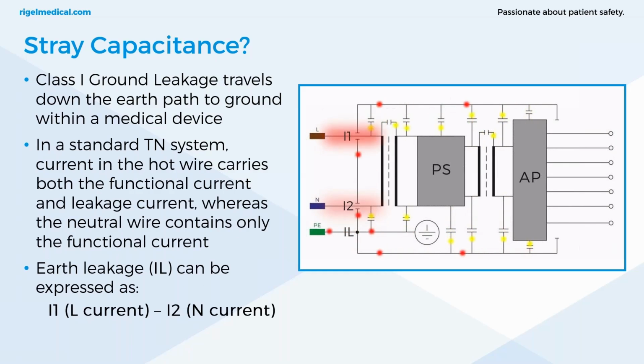So class 1 ground leakage travels down the earth path to ground within a medical device in a standard TN system. Current in the live wire carries both the functional current and the leakage current, whereas the neutral wire only contains the functional current. There is a method within a different standard, 62353, whereby the leakage current is measured by looking at the imbalance between these two connectors. But the preferred method is to measure it directly. So the live carries the functional and leakage current. The leakage current is lost through capacitance within the medical device. It travels to the enclosure and down the protective earth path, and we can measure that using a safety analyzer.